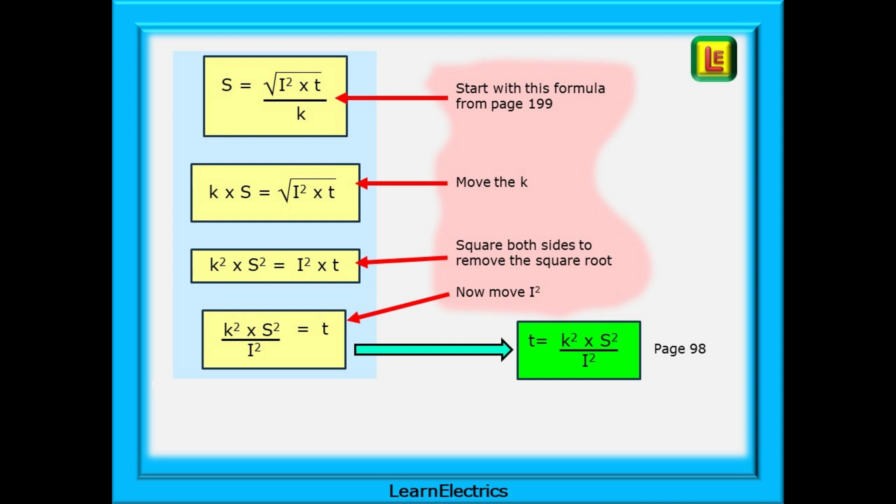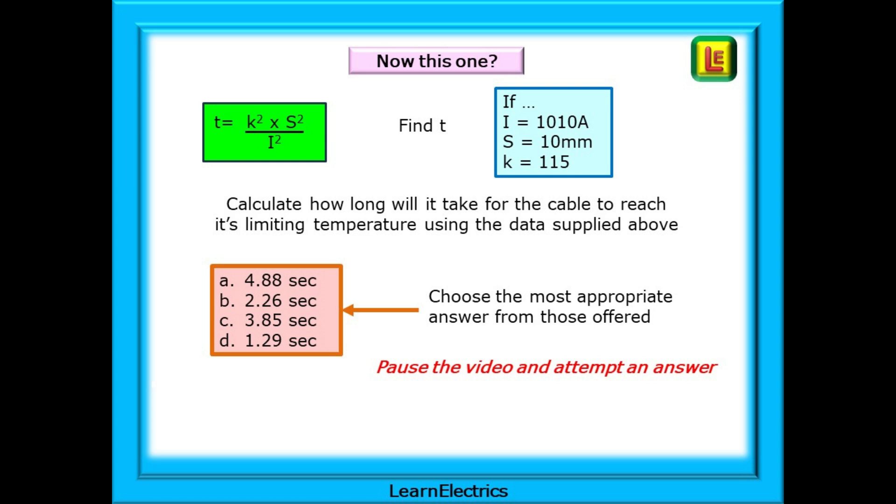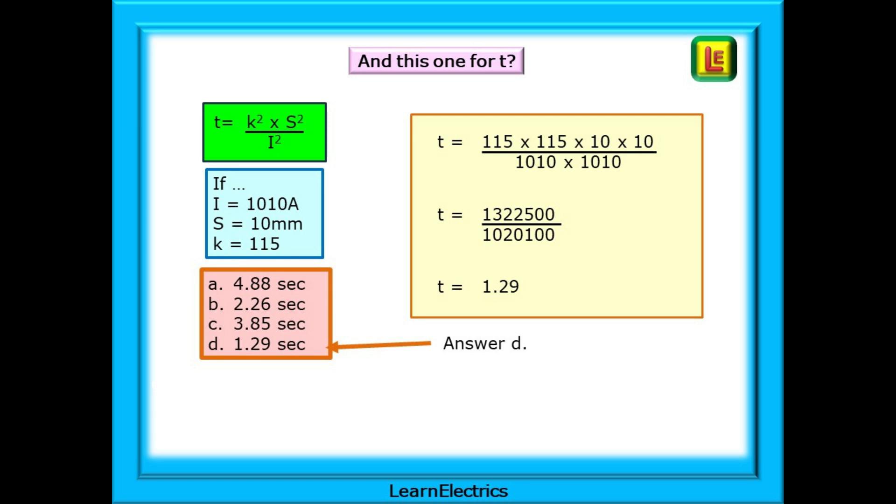Now let's put some numbers to it. Different numbers this time. We need to find the value of T. We are asked to calculate the time, how long it will take for the cable to reach its limiting temperature using the data supplied in the blue box above. And then choose an appropriate answer from the four options available. Pause the video while you attempt the question. The answer is on the next slide. Follow our working out and the method we've used. Squares of numbers are just the number multiplied by itself. 10 squared is just 10 multiplied by 10. And shown here is an easy way to calculate with squares of numbers. You should have an answer of about 1.29 seconds, answer D. The answer is telling us that, with this amount of fault current, a 10 mm earth conductor will reach its 70 degree temperature limit in a little over one second.